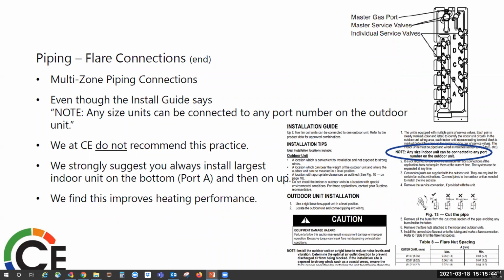Any size of unit can be connected to any port. Just remember the right number. It is recommended that you put the largest unit on port A. This is a good idea. It helps in heating performance. But if all the heads are the same size, it's not going to matter as long as you know which one's going where.